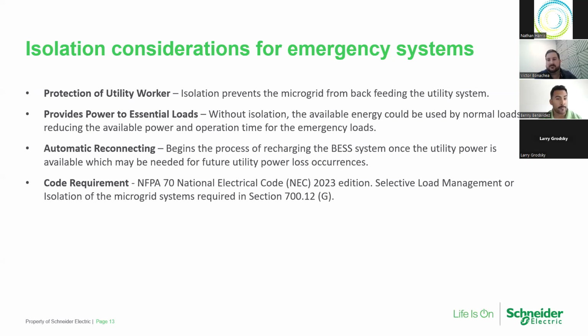Another point of consideration for isolation systems is you can provide power to your essential loads. So if you look at our block diagrams, with an automatic interconnection switch, you're isolating a portion of your electrical facility for backup power to your energy storage system, whereas conventionally, you would provide power to your entire system. And as you know, battery energy storage systems have a finite duration of power. So if you're going to utilize it as a backup power source, you've got to make sure you section off the essential loads so they can get power. Automatic reconnecting eliminates the process of manual intervention, and you can safely, automatically disconnect and reconnect to that primary power source once it's returned.